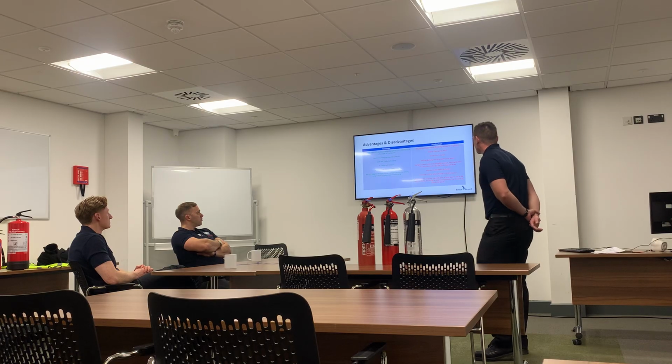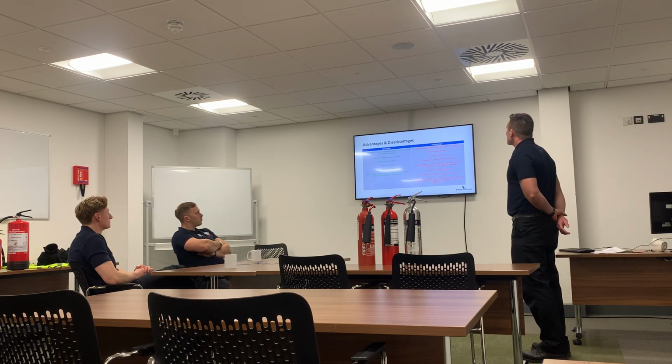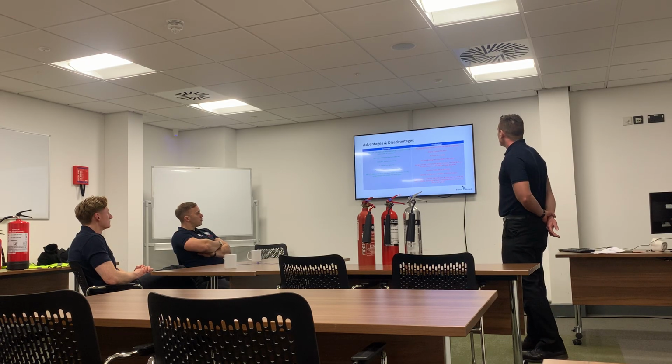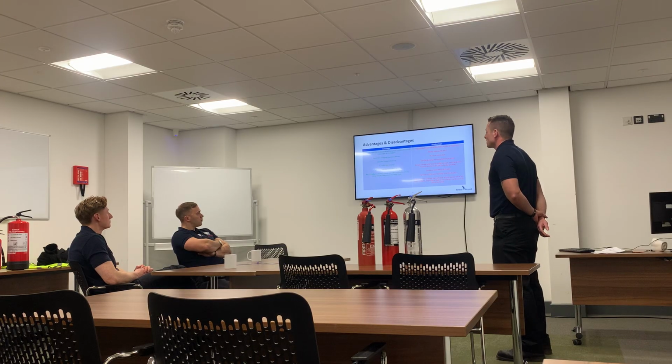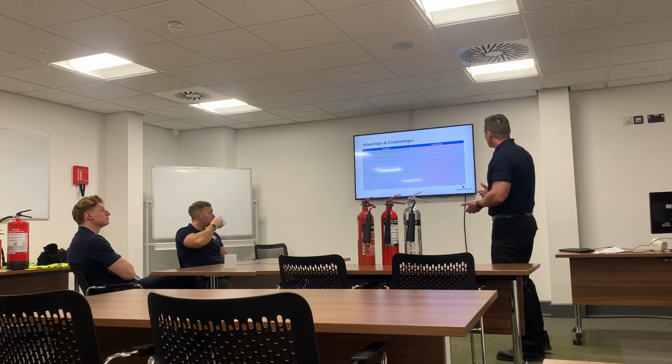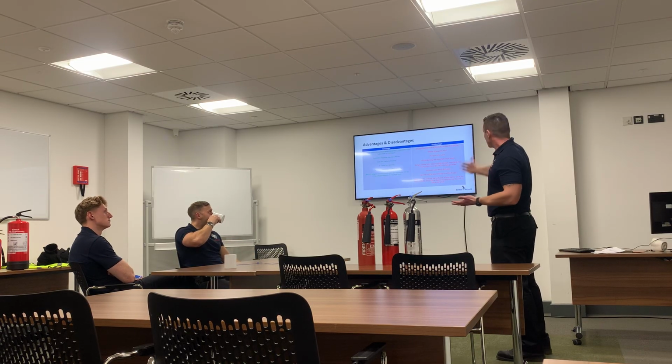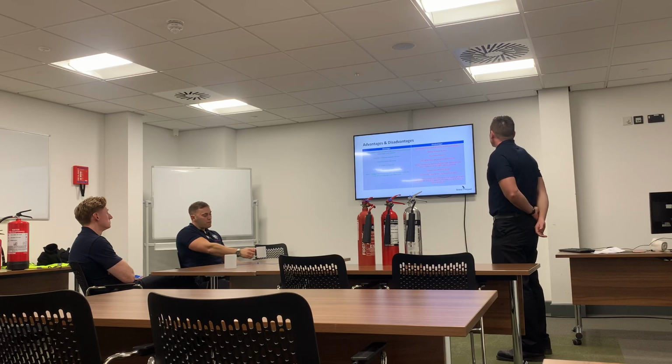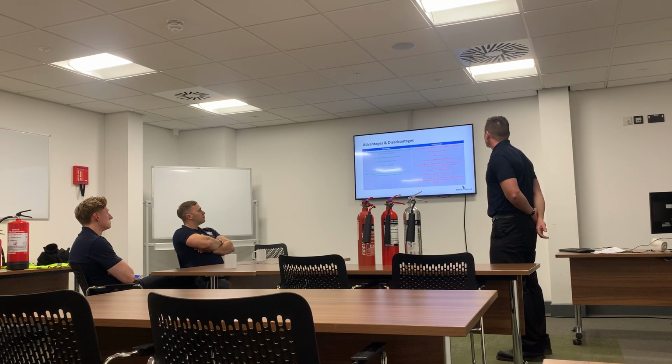So some disadvantages: there's no post-discharge control, so no ability to prevent reignition. Again, that could come down to the cooling effect, or if oxygen is reintroduced, that could be by wind, etc. It could push the CO2 agent media out of the way. It's readily dispersed by wind, as mentioned. Reaction with metals, and possible discharge of static electricity at the nozzle, so it's important to note that.